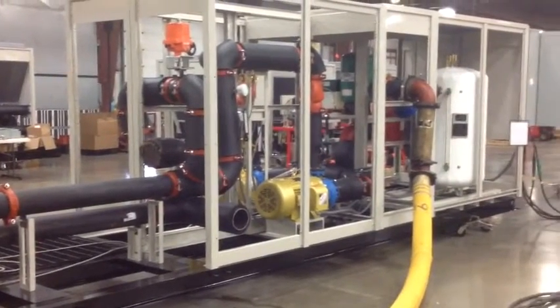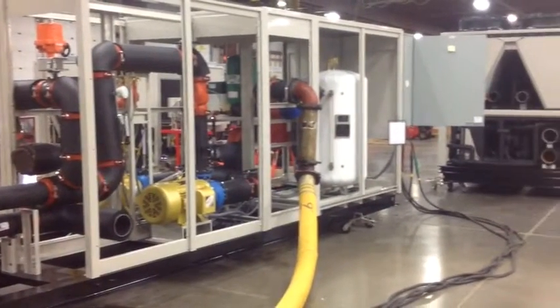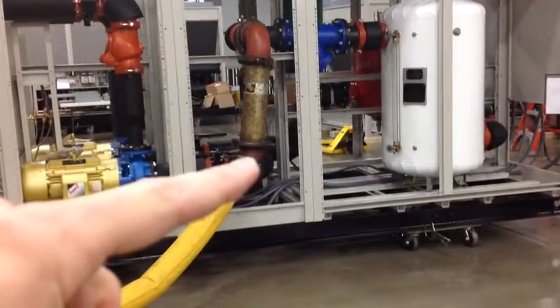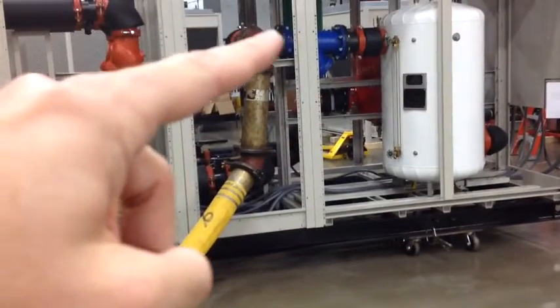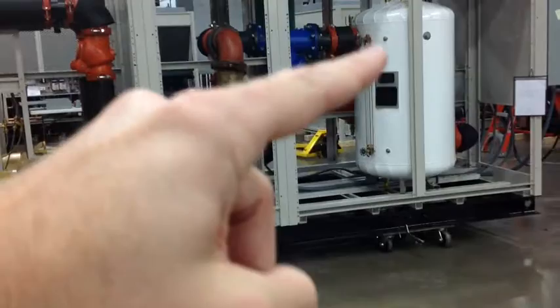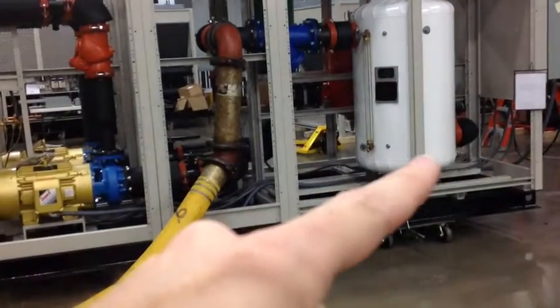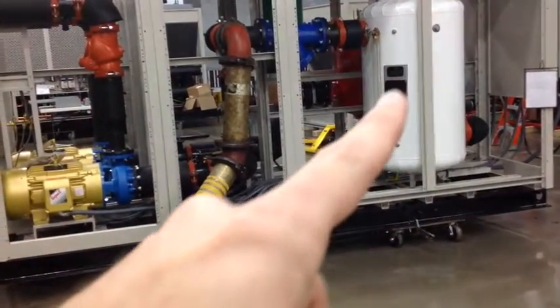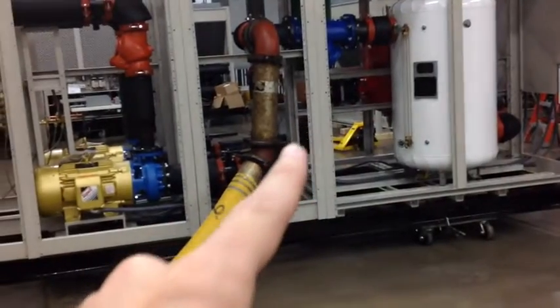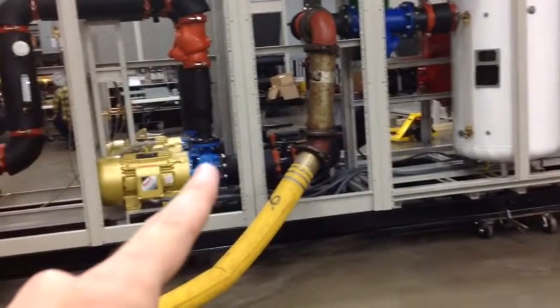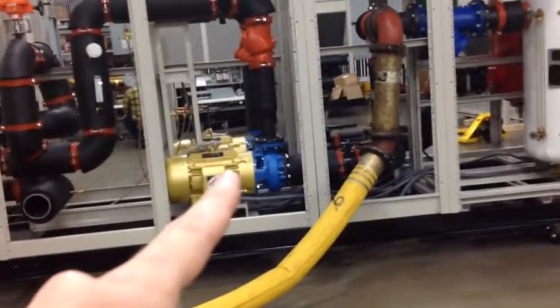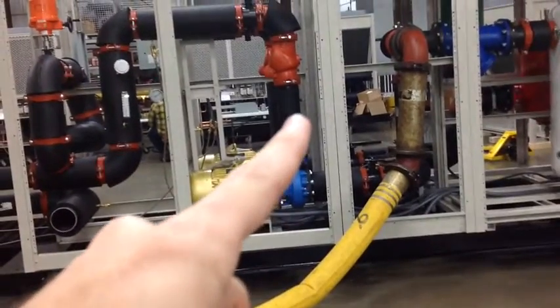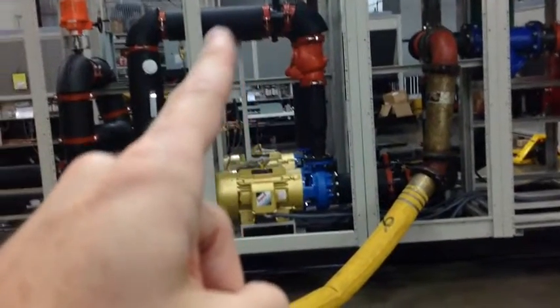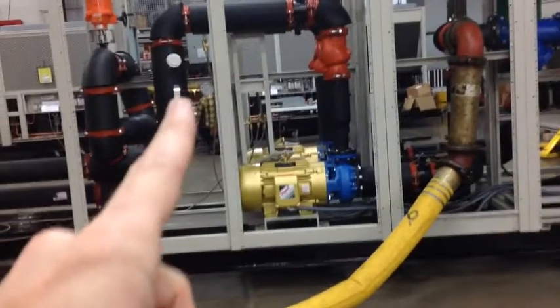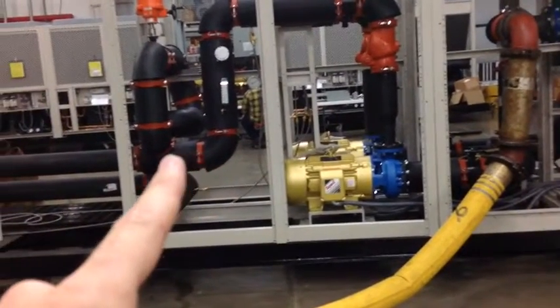As we pan right, we see the pump and auxiliary array. Now we'll take a tour of that. Water comes in the return connection, through the strainer, into the tank, goes out of the back of the tank and through the air separator, which we can see in the background in the red, down into the pump suction, vertical pump discharge, up through the check valves, and over into the discharge, which feeds through the future free cool section.